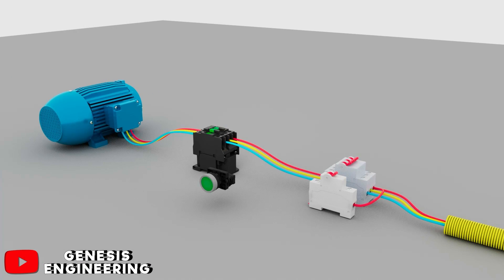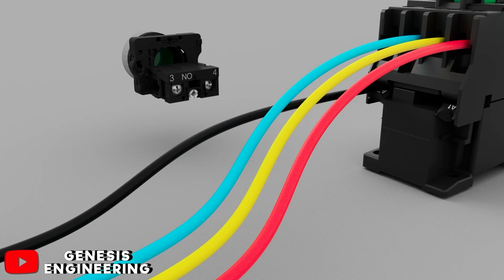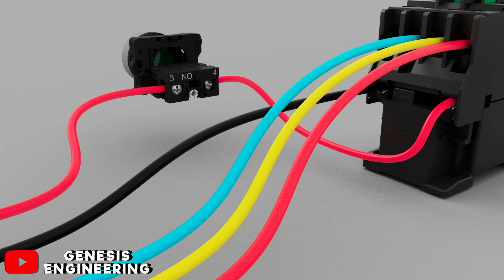We connect the direct neutral to A2 of the contactor coil, then we connect the other phase to terminal 3 of the green button and output another phase to terminal 4 of the button to A1 of the contactor.